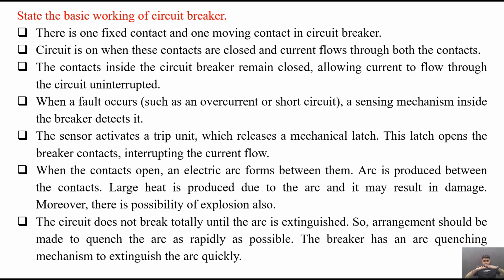When the contacts are open, an electrical arc forms between them. An arc is produced between these contacts. Large heat is produced due to this arc and it may result in damage. Moreover, there is a possibility of explosion also. The circuit does not break totally until the arc is extinguished. So, arrangements should be made to quench this arc quickly or rapidly, as early as possible. The breaker has an arc quenching mechanism to extinguish this arc quickly. So this is how the basic working of a circuit breaker is explained to you.